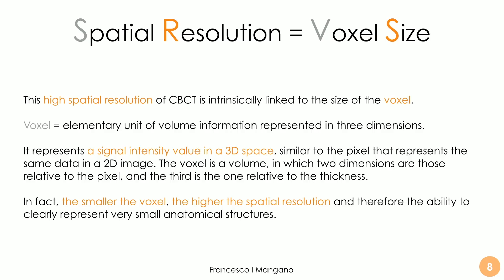So what is this spatial resolution? Basically, it's the voxel size. The higher spatial resolution of CBCT is linked to the size of the voxel. The voxel is the elementary unit of volume information represented in 3D; it represents a signal intensity value in a 3D space. It is similar to the pixel for 2D, but here we are in 3D. The voxel is a volume in which two dimensions are relative to the pixel, with a third dimension being the thickness. The smaller the voxel, the higher the spatial resolution and the ability to discriminate between small anatomical structures.